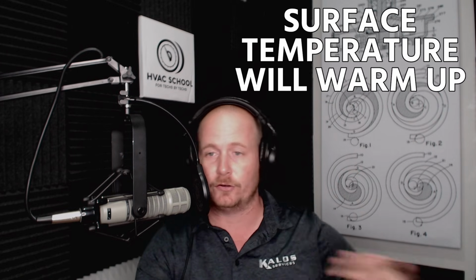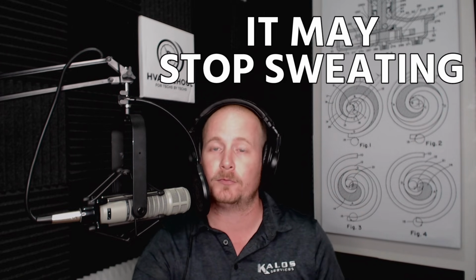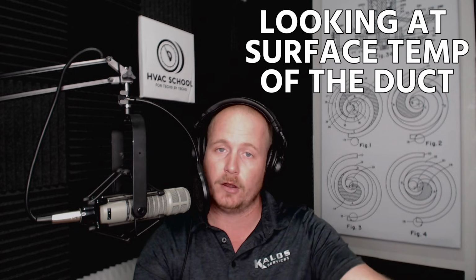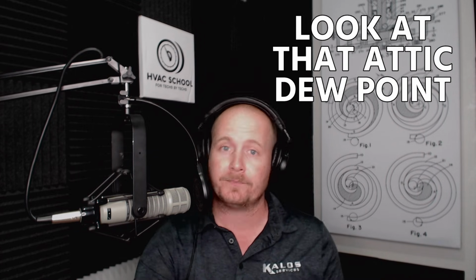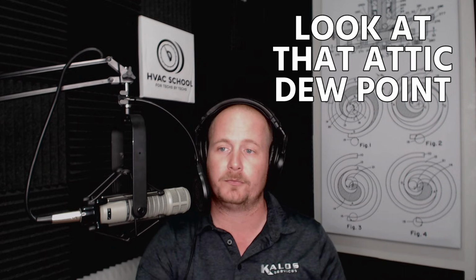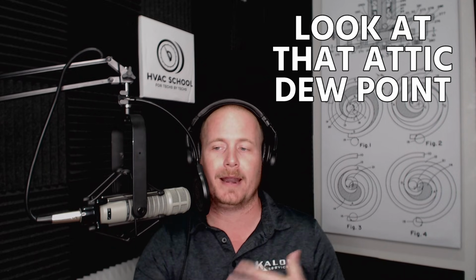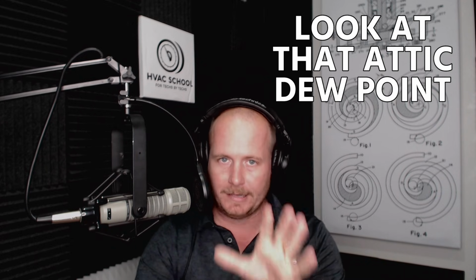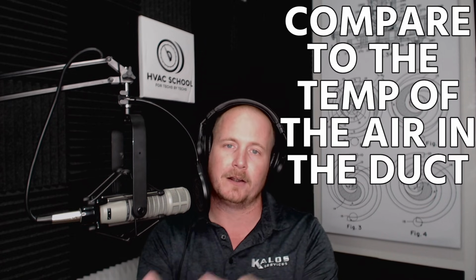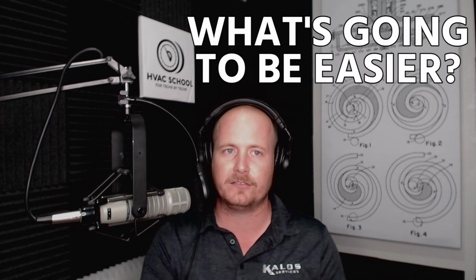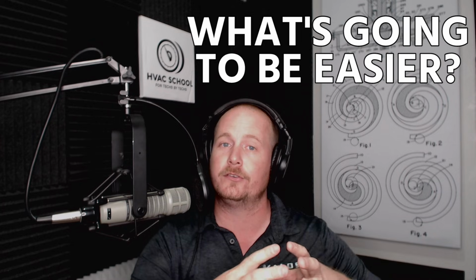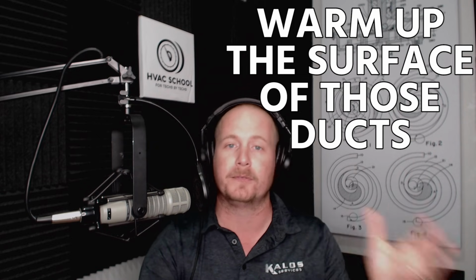You fix that airflow problem, increase the airflow, and then the surface temperature of the duct will warm up and it may stop sweating. But that's where looking at the surface temperature of the duct as you can and looking at that attic dew point, that's where I would always start whenever you have anything sweating in an attic or in a crawl space or in a basement. I often talk about attics because in Florida that's what we've got. That's the place you start, is look at that dew point, compare that to the temperature of the air in the duct, and see what's going to be easier. Is it going to be easier to drop the dew point of the air in that attic or crawl space or basement, or is it going to be easier to somehow warm up the surface of those ducts?